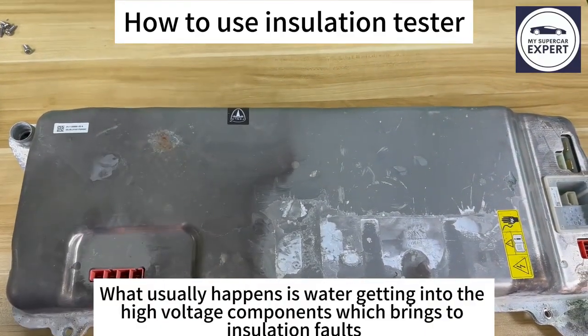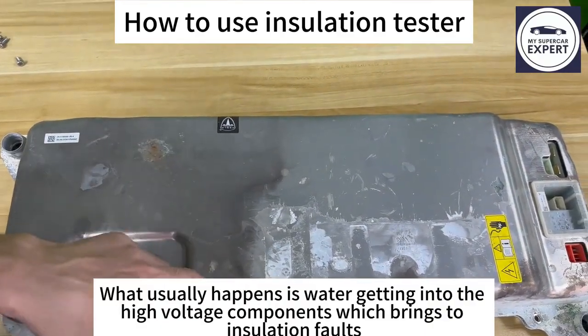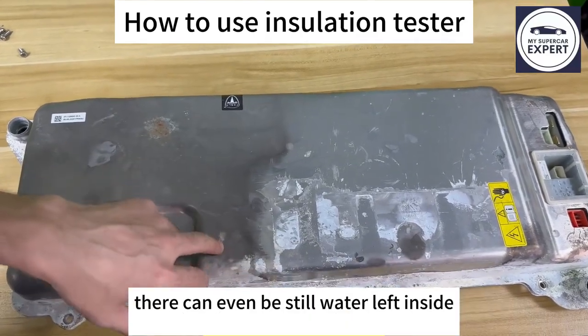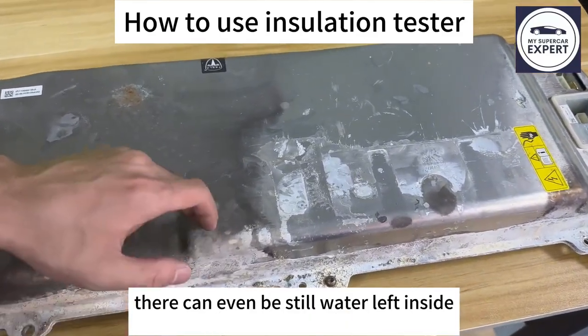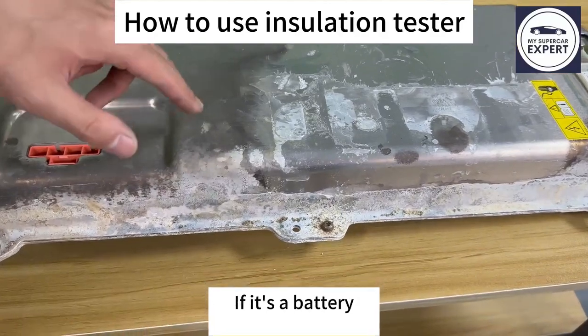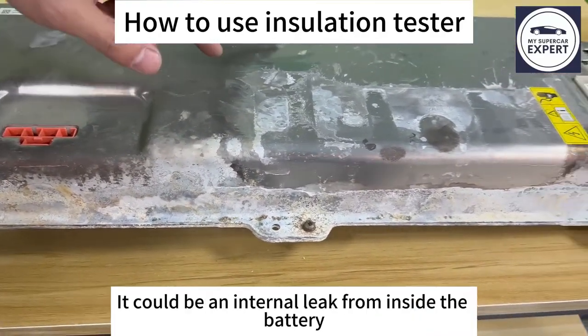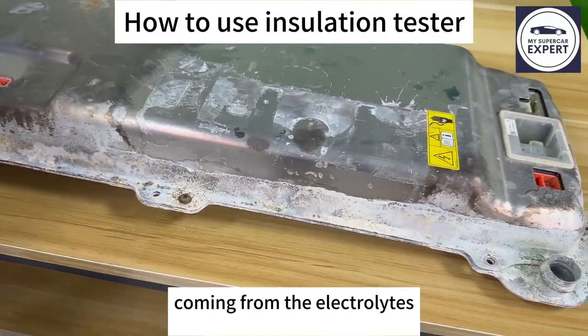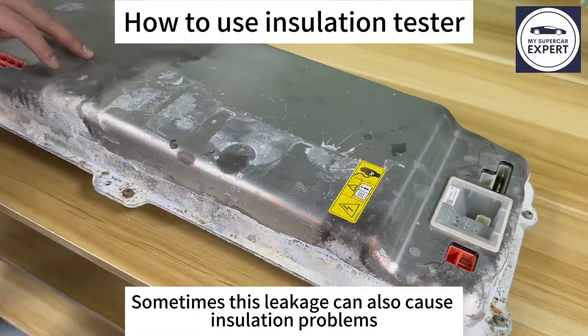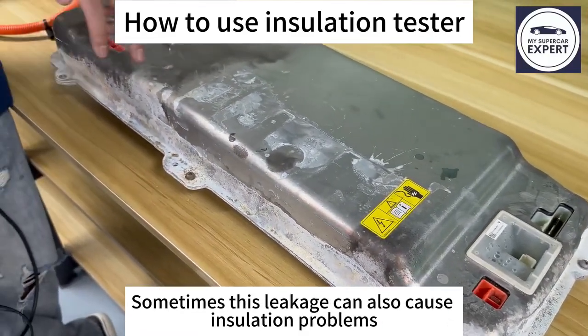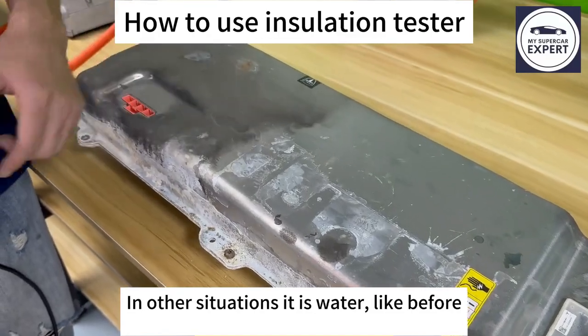What usually happens is water getting into the high-voltage components, which leads to insulation faults. There can even be still water left inside. Another situation is, if it's a battery, it could be an internal leak from inside the battery, coming from the electrolytes. Sometimes this leakage can also cause insulation problems. In other situations, it is water, like before.